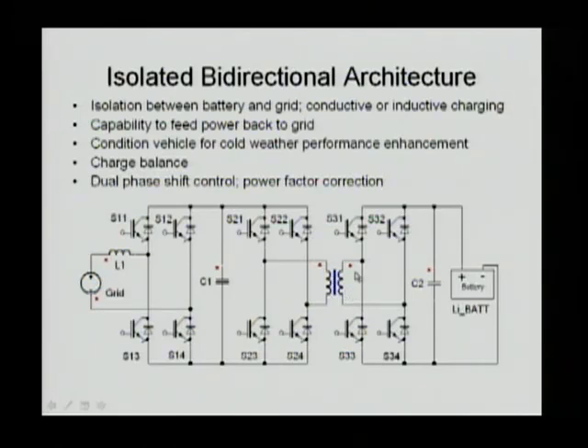The transformer is a high frequency transformer that transfers the high frequency AC from the primary to the secondary. On the secondary, you have another bridge that acts as a rectifier during charging of the battery. During discharge, it acts as an inverter to convert battery voltage into high frequency AC.